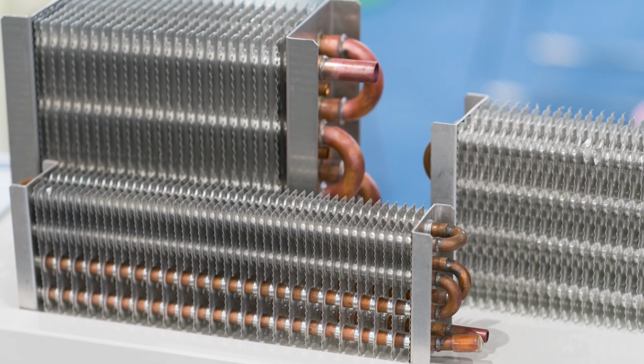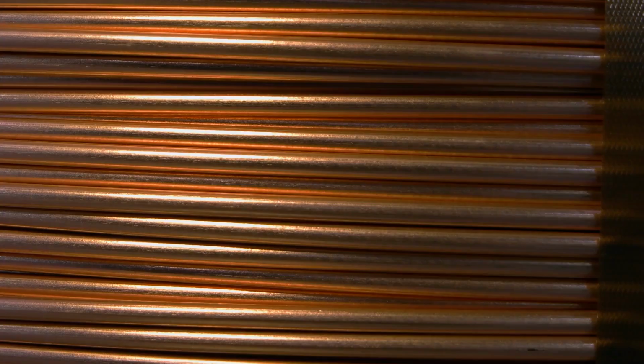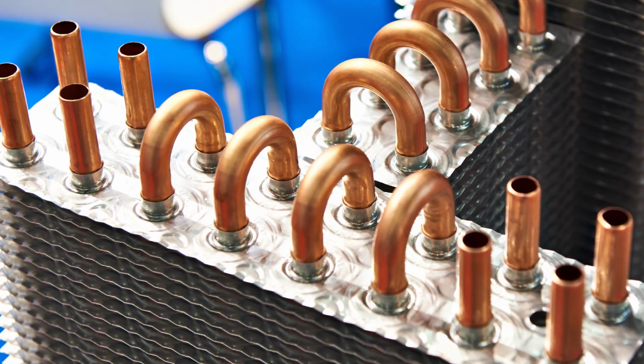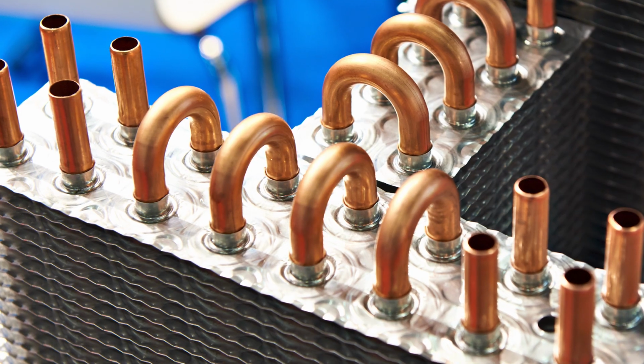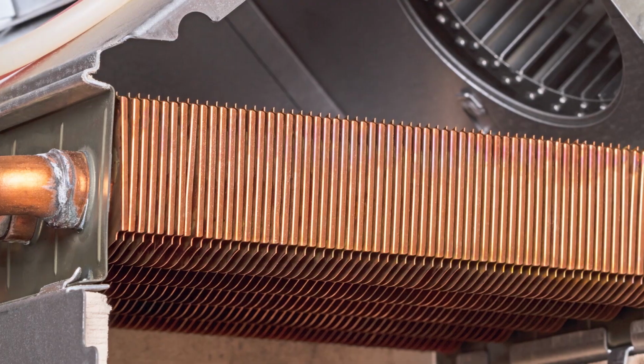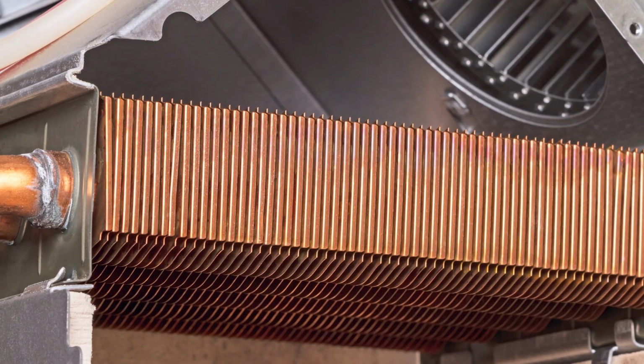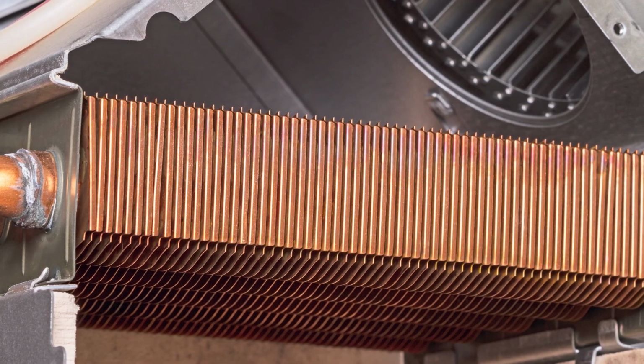Sure, thanks Jeff, great to be here. With the transition to small diameter tube use, especially in heat exchangers, you're looking at quite a few benefits. One is energy efficiency -- reducing the diameter of the tube allows for less material, less refrigerant, more durability, and you're also taking out weight, providing the opportunity to reduce the weight of the equipment.